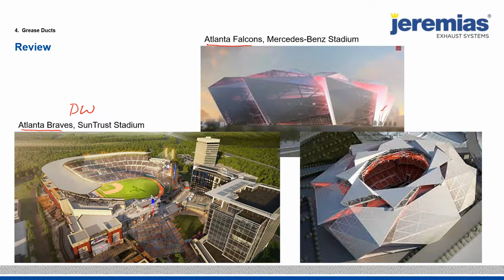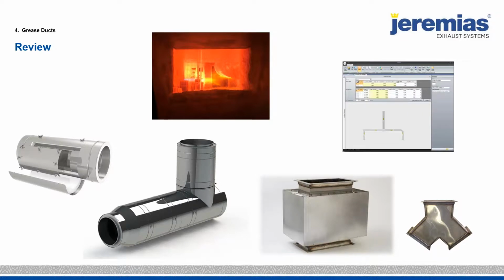So we went back and we supplied single wall on this system, and then the insulating contractor still insulated it like you would the factory, or like you would the field welded. So again, depending upon if it's specified up front or the contractor's involved, sometimes we use single wall, sometimes we use double wall, but always if it's specified up front with the correct factory built systems, the owner is going to benefit in price.